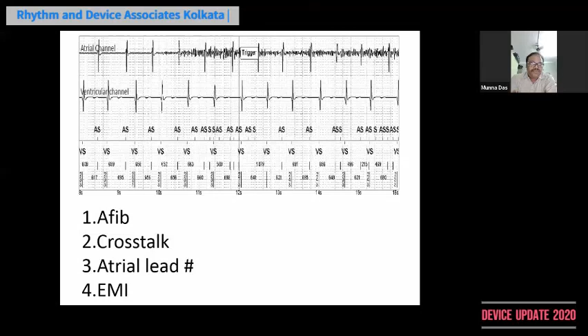EMI could be the answer, but I think it's not, because as you can see, if it was EMI, it would have involved both the ventricular and the atrial channels. So it's not an external source. The atrial lead fracture, where high frequency artifacts can be detected on the atrial channel as also on the marker channel, which senses them as atrial sense events, is the main issue here. And this is a slide to demonstrate the difference between EMI and atrial lead failure. Next slide. Next slide, please. EMI would have affected both the atrial and the ventricular channels, as shown in this particular slide.